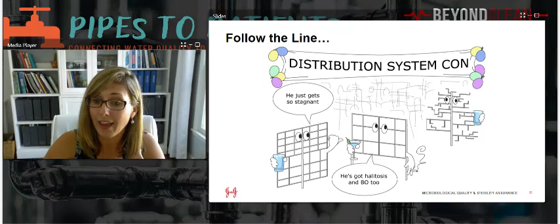So what do we mean by following the line? You're starting at where the water comes out of your tap, and you're following the piping through the distribution loop to identify where there might be points in the piping or faucets specifically that can lead to areas where the water is not flowing. If water doesn't flow, it allows an opportunity for bugs to stop, eat, and grow. So this is where we really start to worry about things like a biofilm.